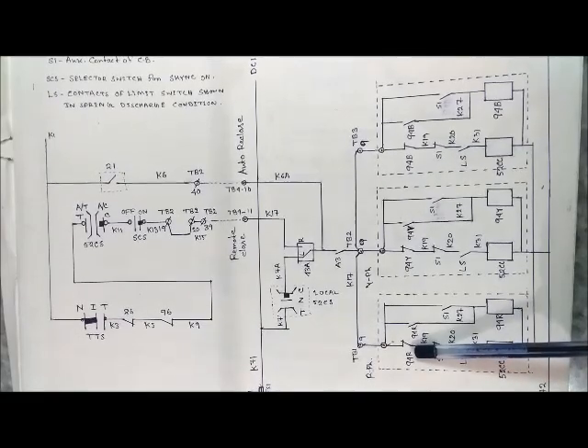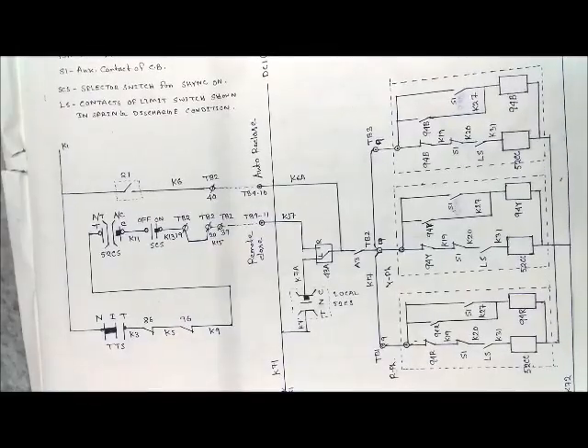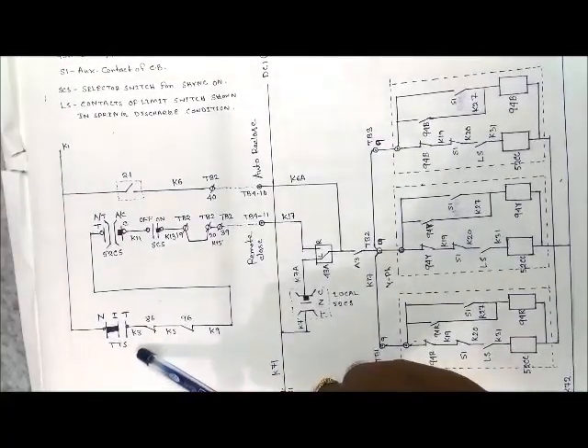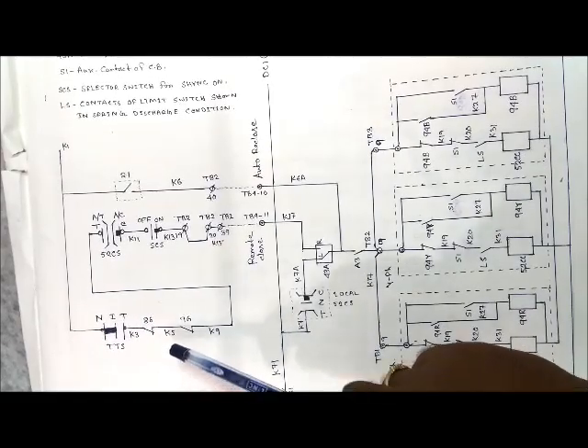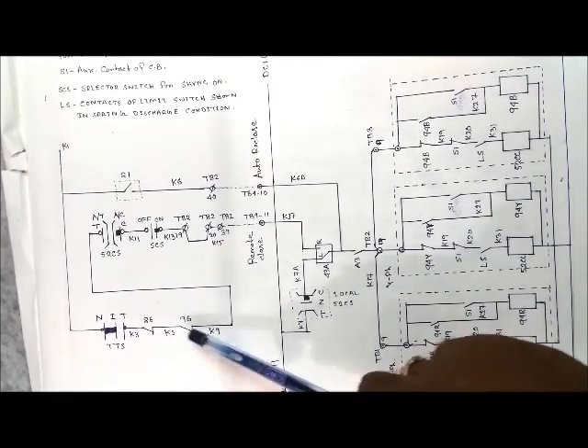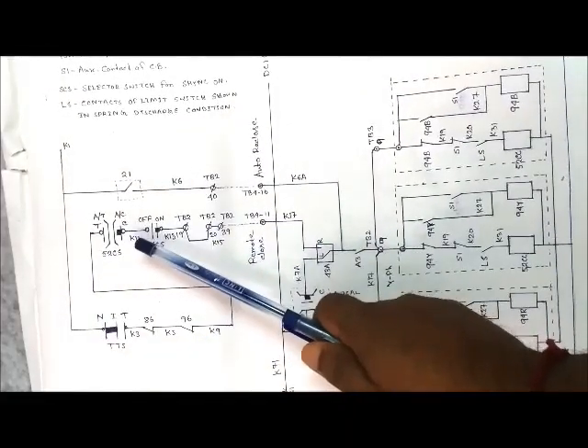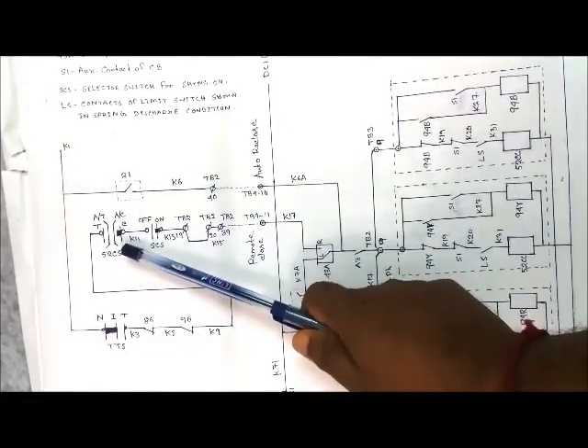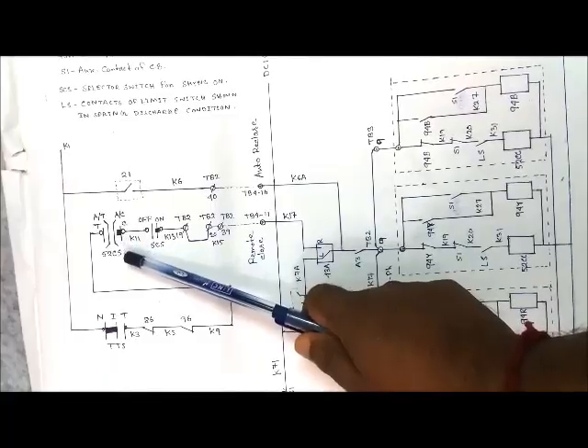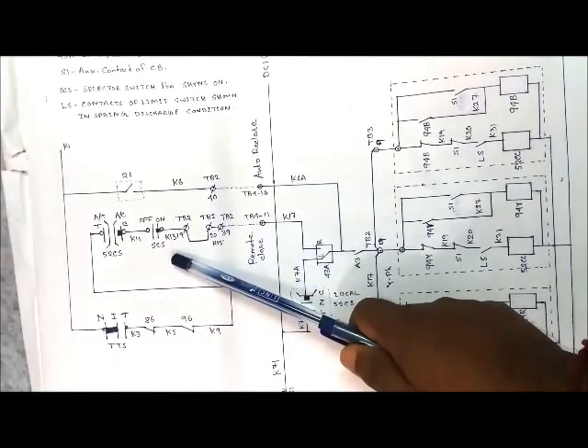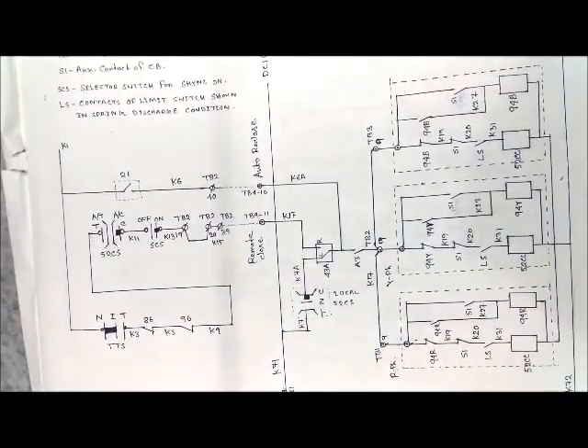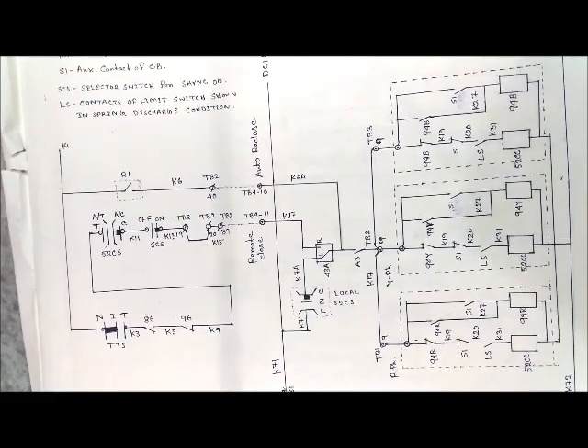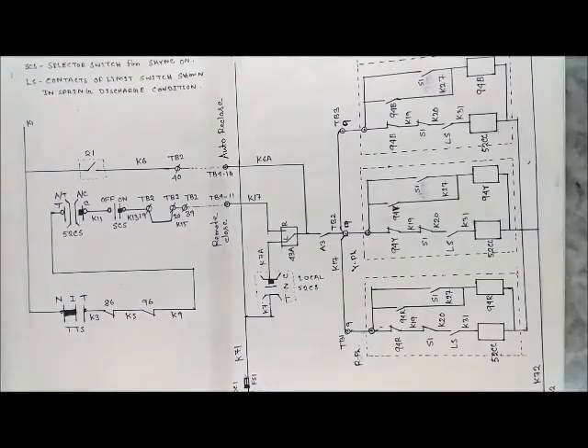In the control and relay panel portion, TTS is the trip transfer switch. In series with the TTS switch there are NC contacts of the 86 and 96 relay, and in series there is the closing control switch located at the control and relay panel. SCS is the selector switch for synchronizing — it must be in the ON condition. Contact 21 is for automatic closing from the distance relay.